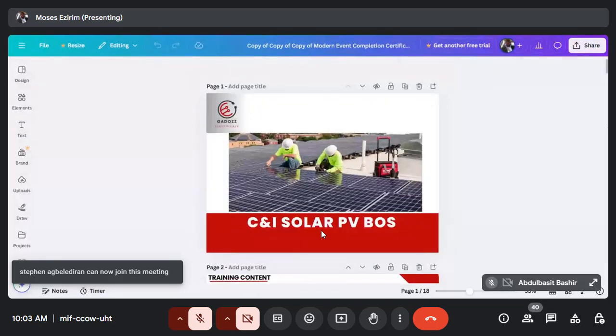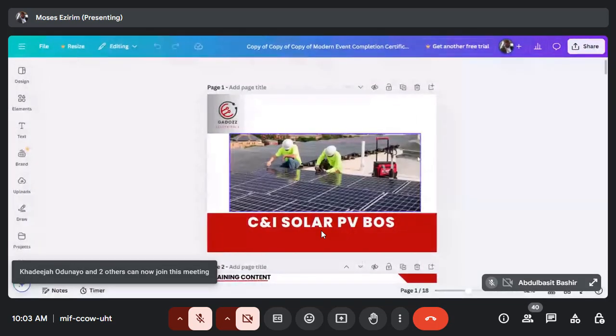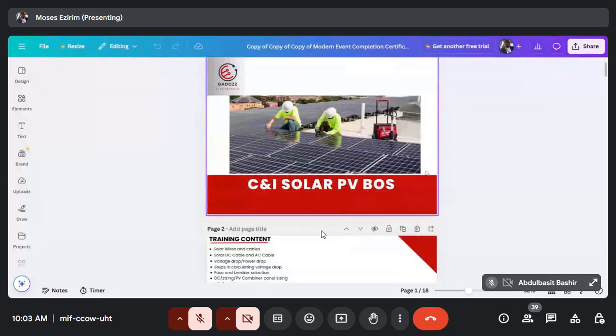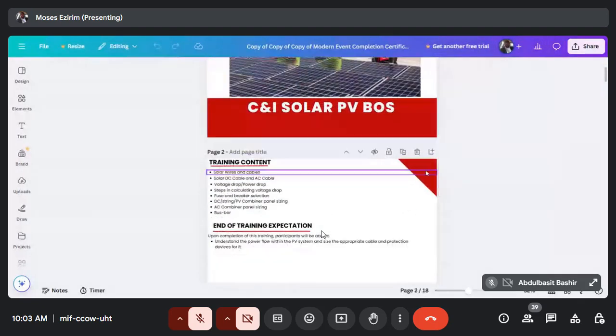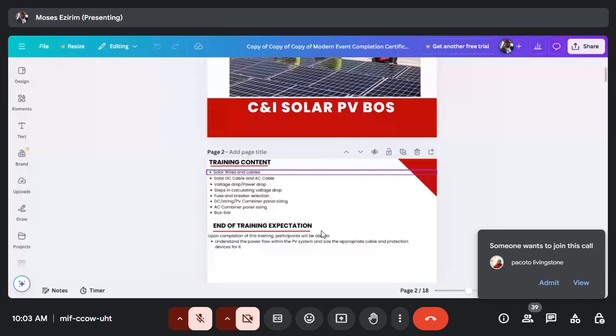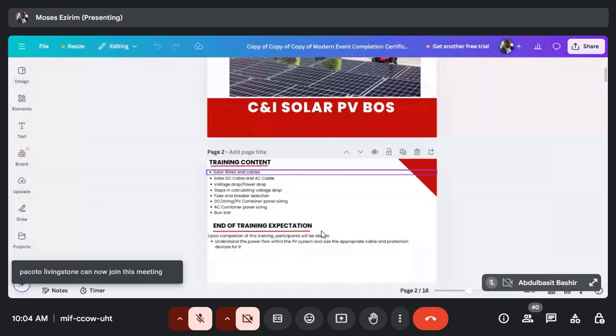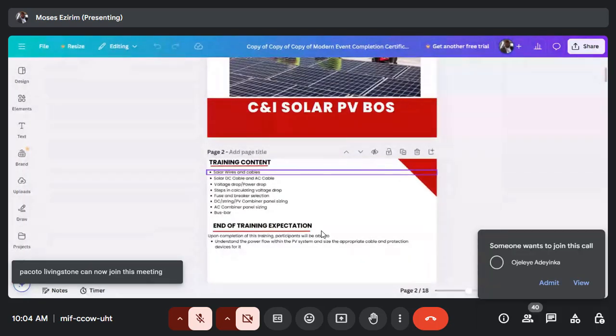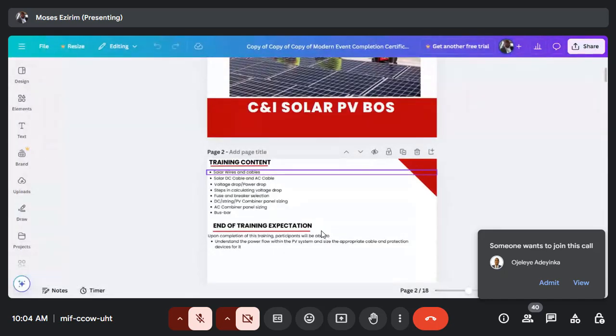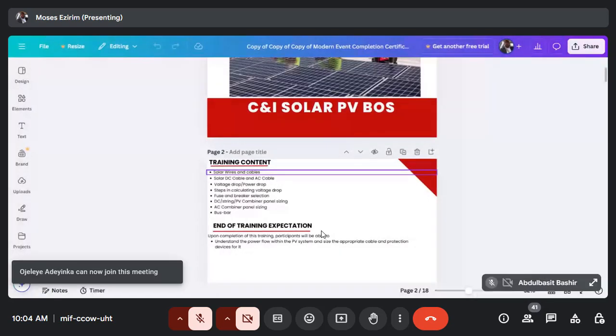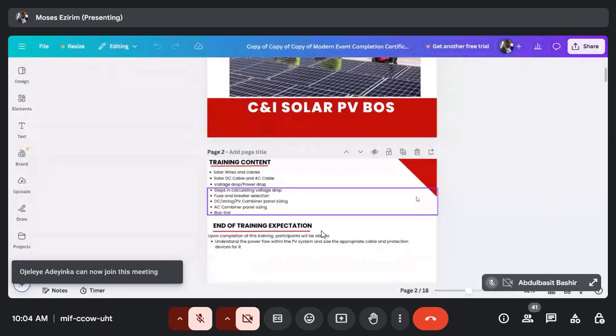All right, thank you. So now we're looking at today's topic: C&I solar PV BOS, that is the balance of system. Basically the balance of systems are: wires, DC cables, AC cables, breaker, surge protector, AC combiner box, bus bar, DC combiner box, earthing, and lightning arrestor.